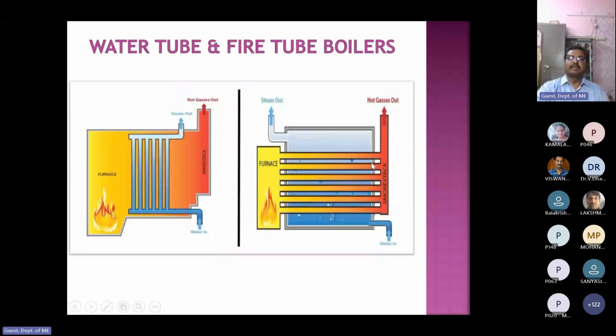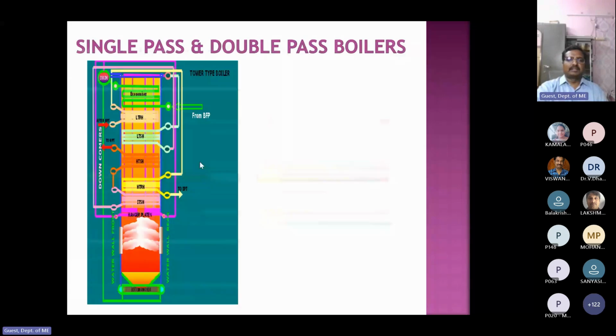In any power plant, almost all power plants use water tube boilers only. High pressure boilers are water tube boilers only. And there are single pass and double pass boilers. This is a single pass boiler. That means there is only one pass from the furnace through the superheater, economizer, and reheater. Everything is installed in a vertical column. It is called a single pass boiler.